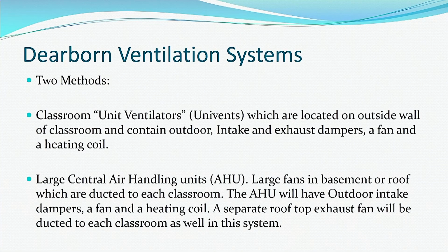So in our Dearborn schools, there's two methods that we have, infrastructures that we have to ventilate our classrooms. One very common one is something called a unit ventilator or a univent. And that's that long thing by the window that we all see on the outside wall of our classrooms. And that unit has a fan and a heating coil and sometimes a cooling coil. And it has an outdoor intake or a grill to the outside through that outside wall. So a unit ventilator draws in outdoor air all day while the school is occupied, pulls in a little bit of air from the classroom as well, mixes the two together, heats it, and then delivers it out the top where that air blows out of the unit ventilator. So all of our classrooms that contain unit ventilators are getting fresh air delivered by that unit ventilator all day long. Coupled with that typically would be an exhaust fan on the roof where some percentage of air would be exhausted all day long as well. So that's a very common infrastructure in many of our schools.